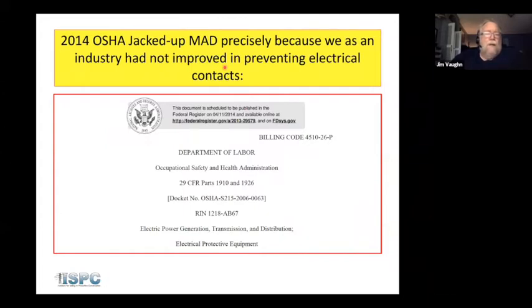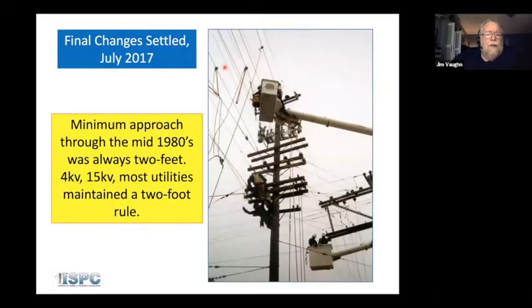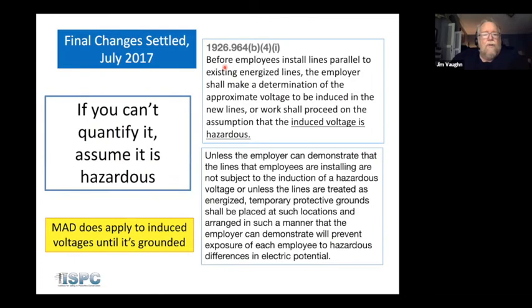So even the distribution voltages had very high MAD that were calculated against TOVs, but it turns out that TOV isn't a big deal in distribution, but it still applies to transmission. All the way up through the mid 80s and all the years that I was working, we always used 2 feet for 4 and 15 kV, and most utilities used the 2-foot rule, and I worked there just fine. But now we're all the way up to more than 2 feet, and sometimes out to 3 feet. Now, the other part is that.